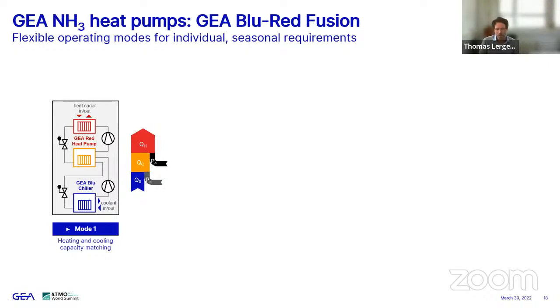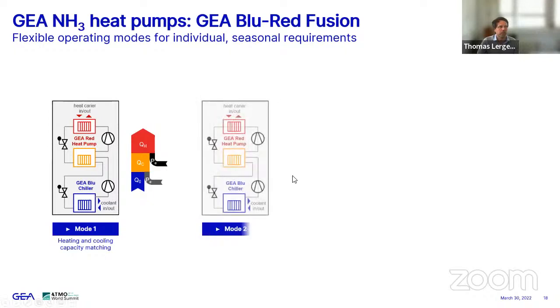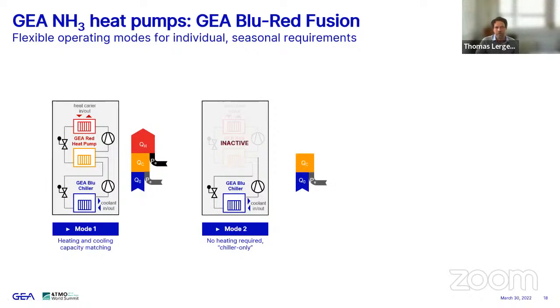Otherwise it doesn't work. However, with this system, we are able, for example, to go in a second mode where no heating capacity is required. So this means you can only operate the chiller and switch off the heat pump stage. Then you're still getting the heating energy from the chiller stage, but unlike in this first mode where all this orange intermediate capacity is injected into the heat pump stage, here we don't have that requirement. So the product is prepared that this waste energy, in this case, is dissipated through a secondary external condensation system. So you can attach a secondary condenser to the system.